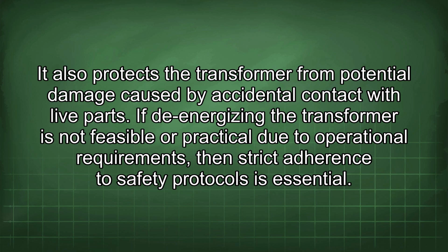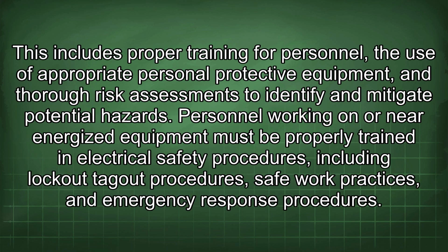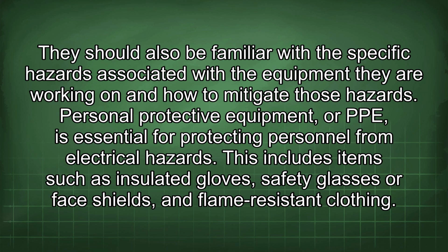If de-energizing the transformer is not feasible or practical due to operational requirements, then strict adherence to safety protocols is essential. This includes proper training for personnel, the use of appropriate personal protective equipment, and thorough risk assessments to identify and mitigate potential hazards. Personnel working on or near energized equipment must be properly trained in electrical safety procedures, including lockout-tagout procedures, safe work practices, and emergency response procedures. They should also be familiar with the specific hazards associated with the equipment they are working on and how to mitigate those hazards.